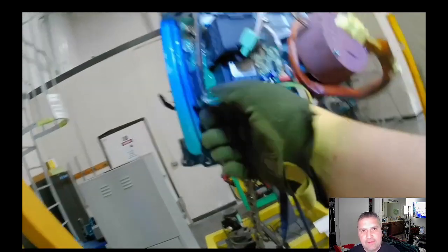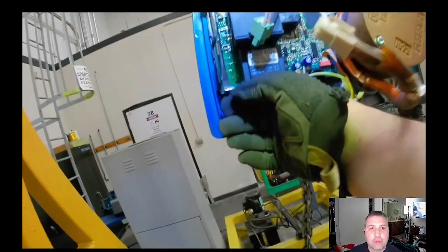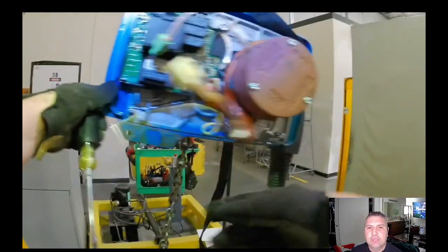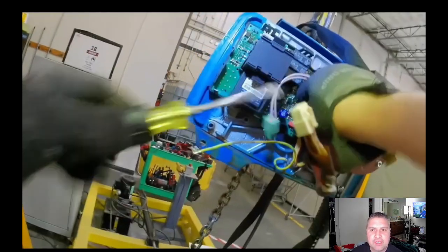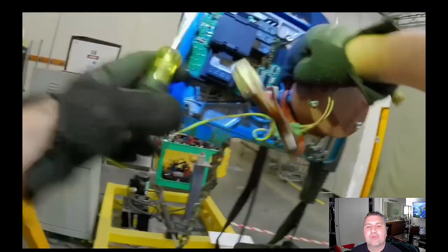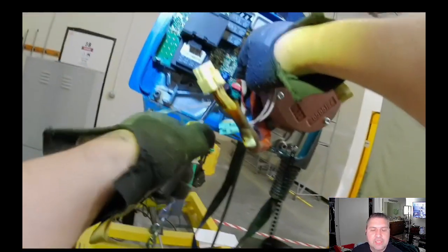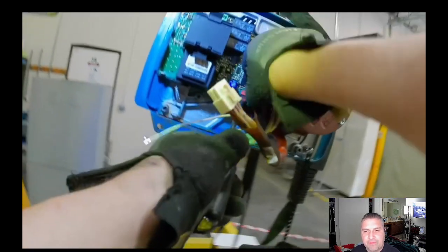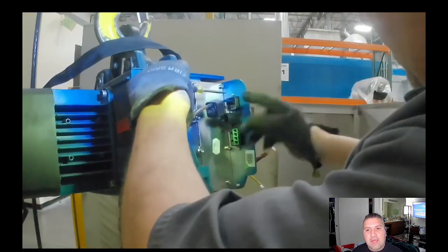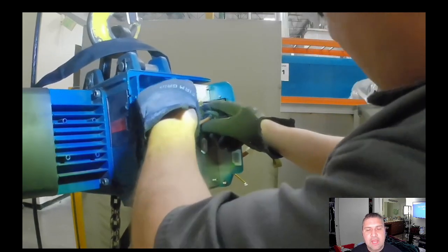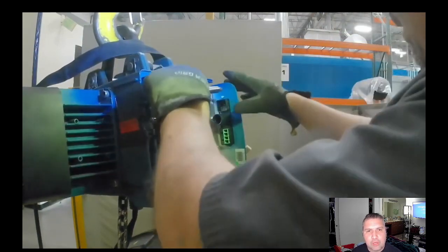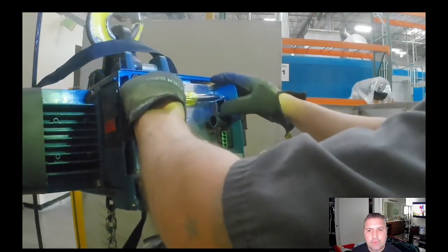So right now I happen to get lucky and have another control board off of another hoist that was very similar to this one. So I'm gonna give it a practice shot. I'm gonna remove this board and try to install another board just to see if I gain function off of it. And then I'll know for sure that I need to order a new board for this hoist, and then I'll proceed to getting part numbers and placing an order for the customer.